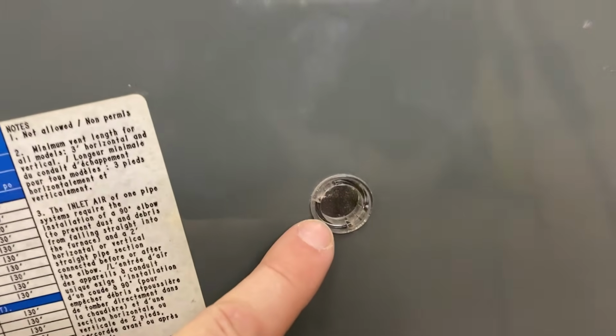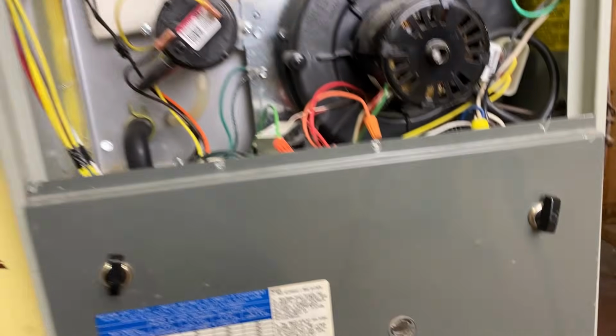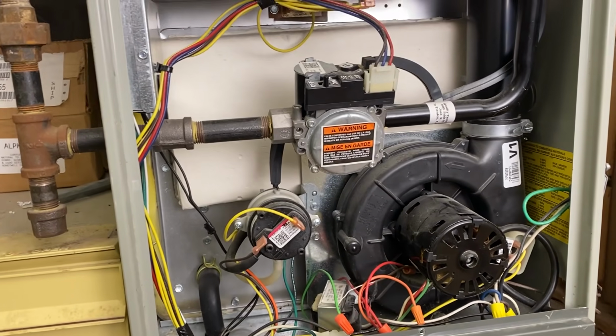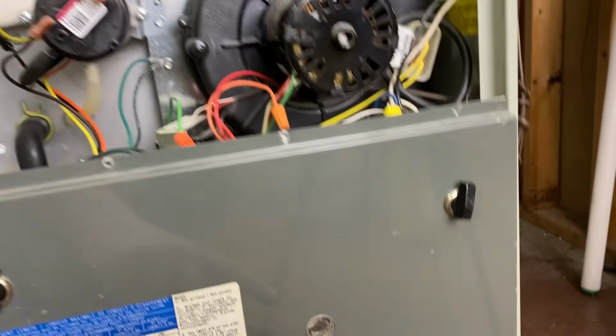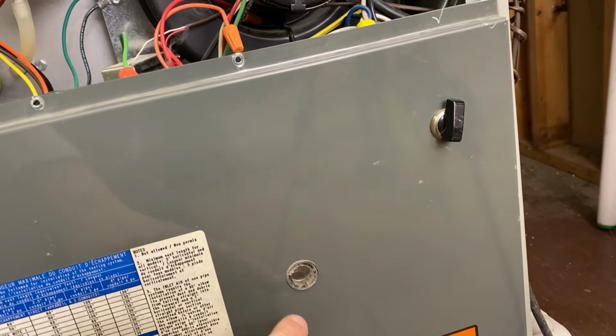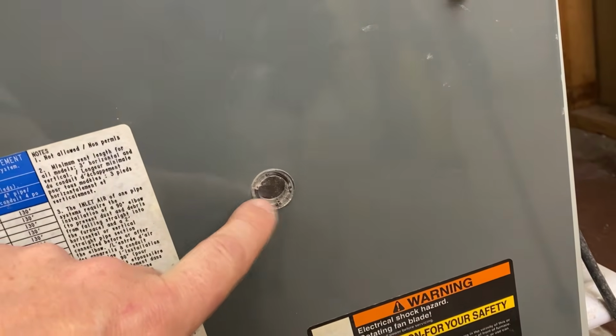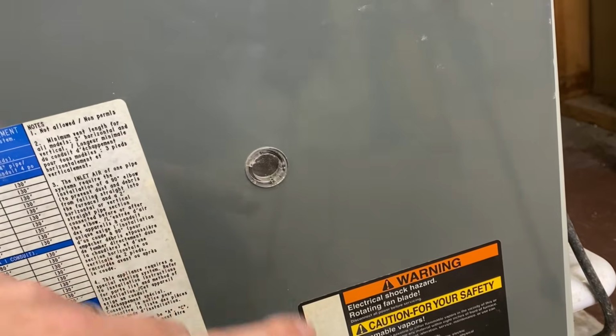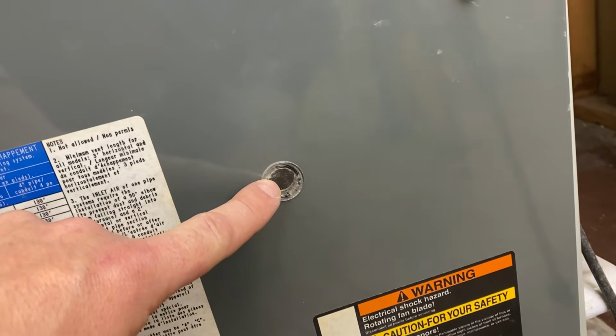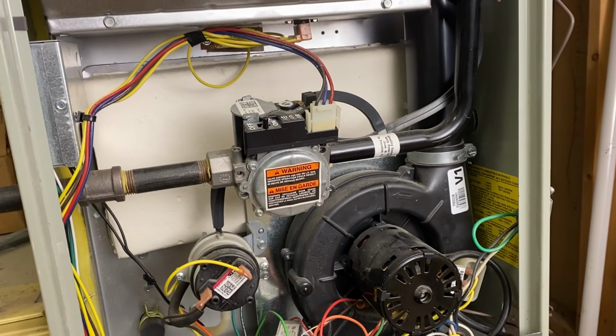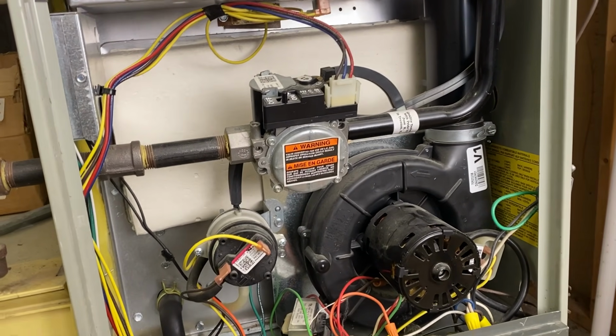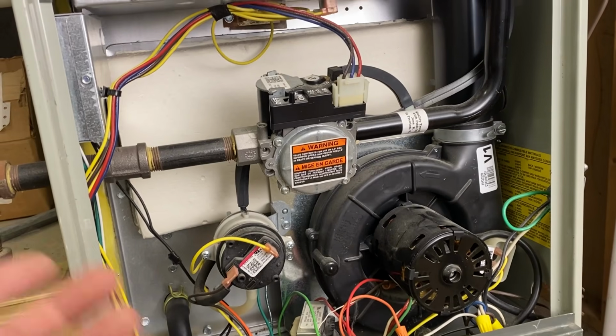The first thing you want to check is this. I have it turned off right now, but if your furnace is not running, you'll hear it maybe kick on and then kick off, and you're not getting heat. After a while it will usually trigger off, or go into just a blower mode. And this right here will give you a blinking light. You'll see that light blinking in there. It flashes a trouble code, which you can look up, and it will tell you exactly which sensor. Once you know which sensor is failing, it'll help you identify the problem. In most cases, it's pretty simple to identify what's wrong.